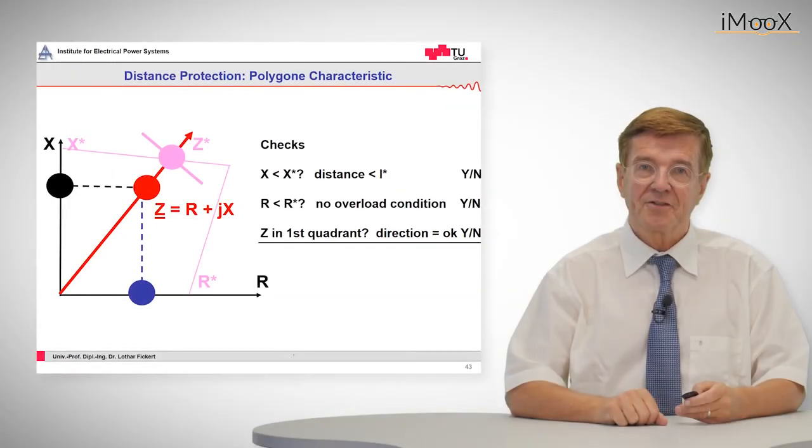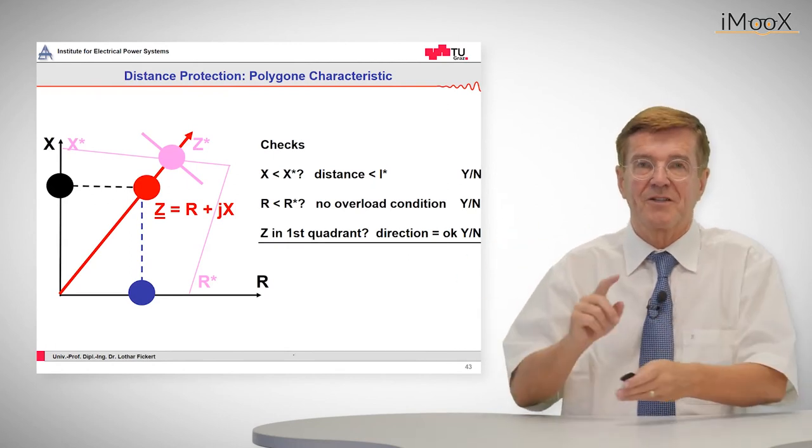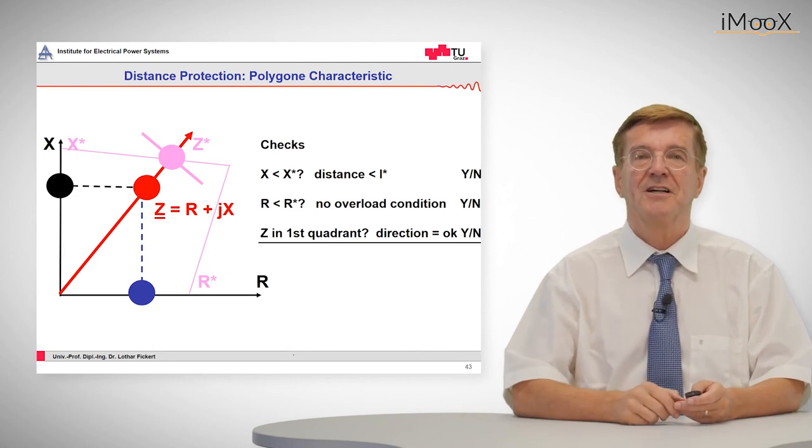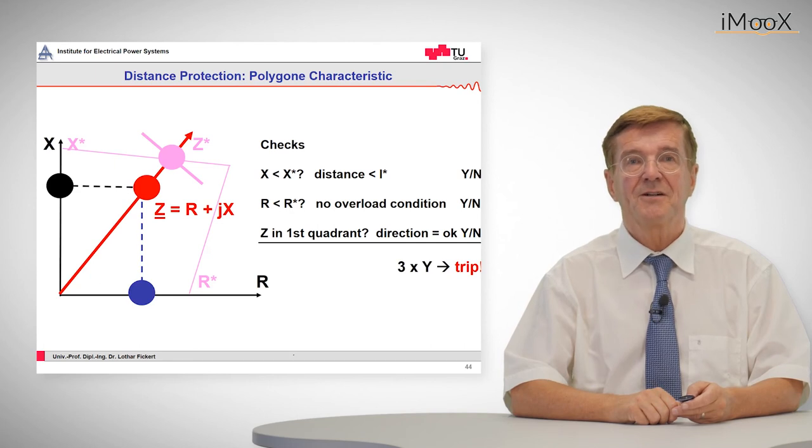And the third condition is, is the whole impedance lying in the first quadrant. That means that it is forward, that is downstream, and not in the reverse direction which would mean restraining. Now if these three conditions are fulfilled we have a trip.